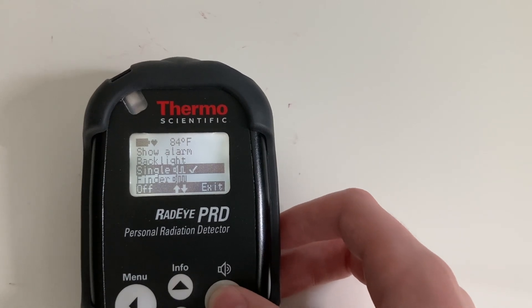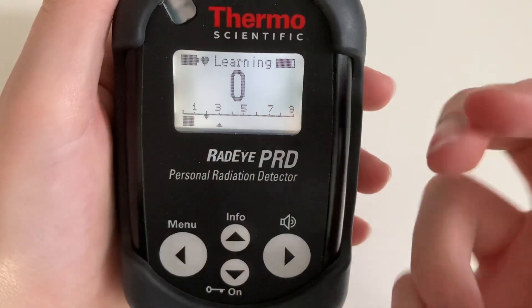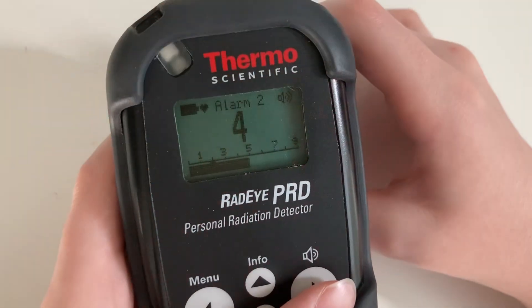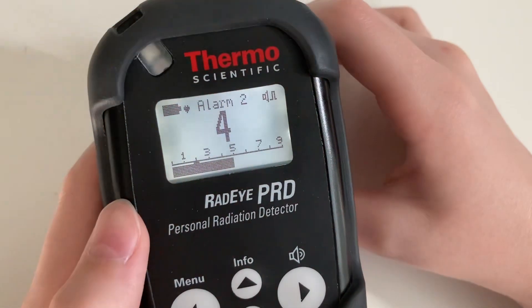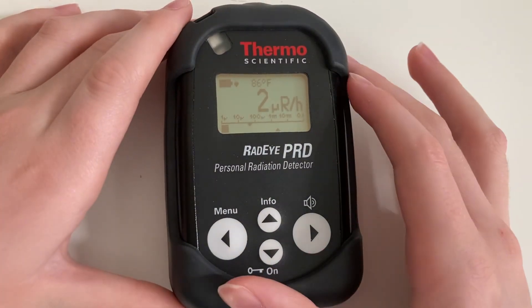I typically use it in the single pulse mode. Another feature of the RadEye PRD that the RadEye Code doesn't have is a level mode. This goes from level 1 all the way up to level 9, and it basically tells you the radiation through a level number — instead of telling you the current dose rate or count rate, it would just tell you level 1, level 2, level 3, level 4, all the way up to level 9 radiation. Those are the reasons that the RadEye PRD is more expensive than the RadEye Code 102.